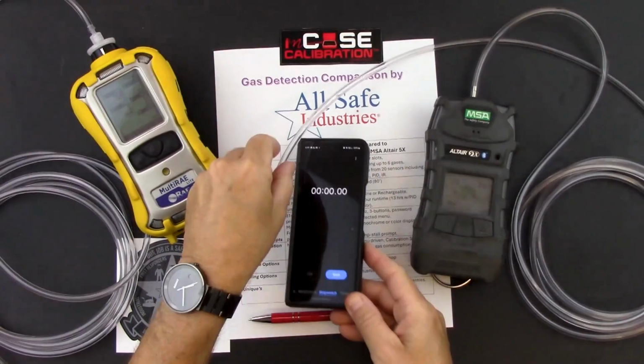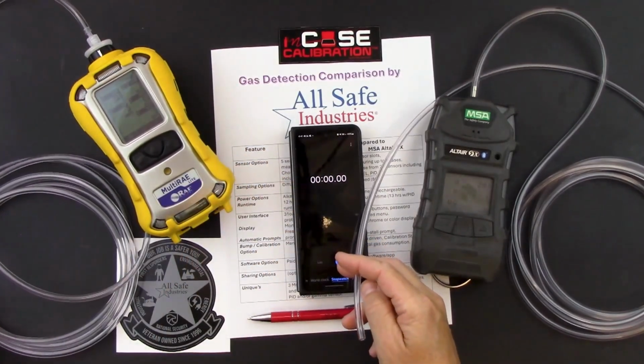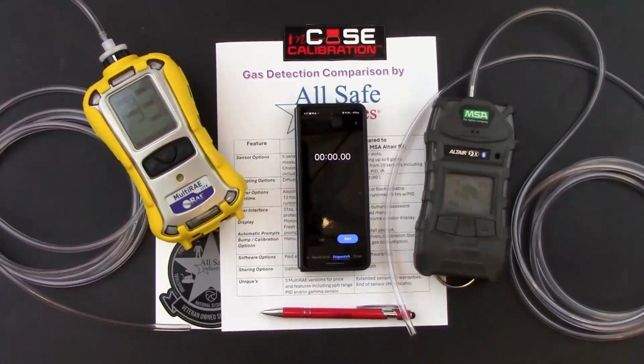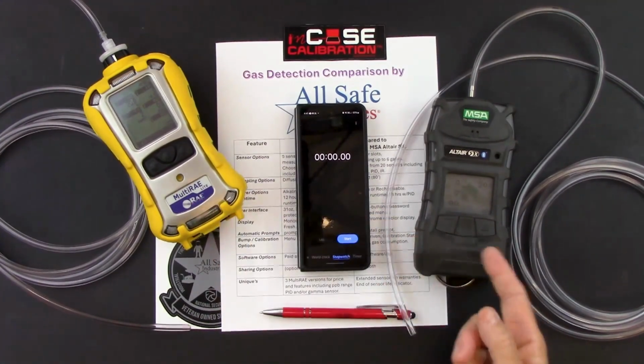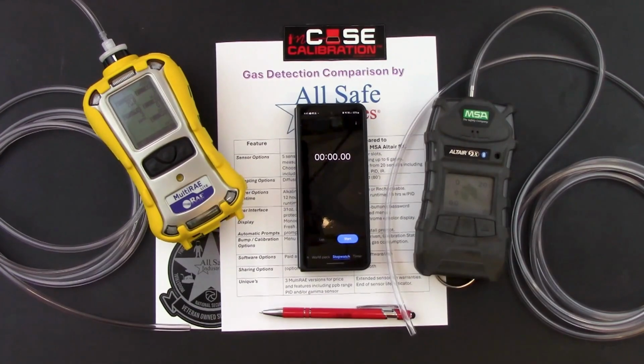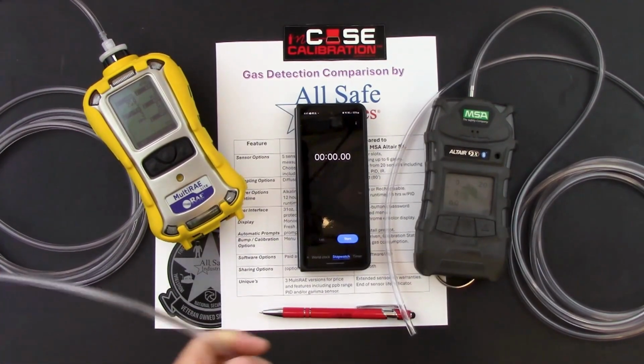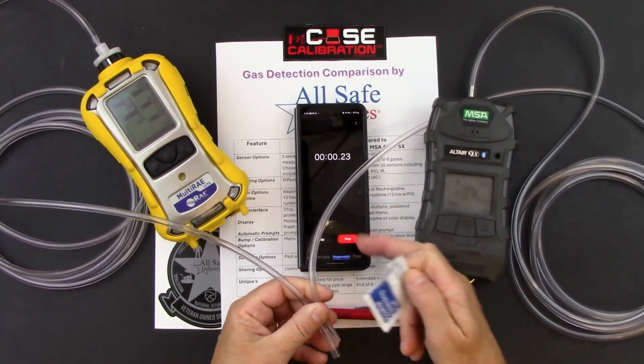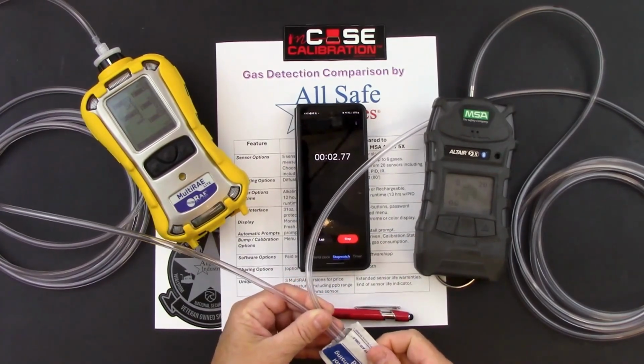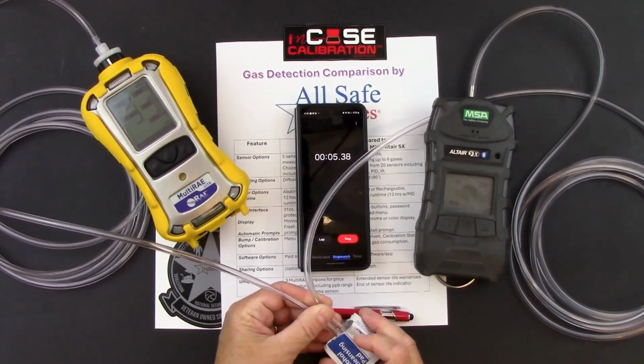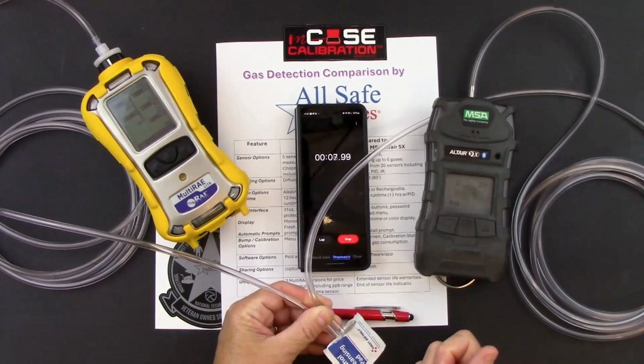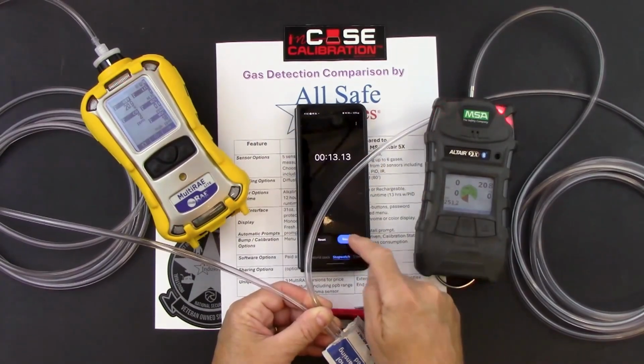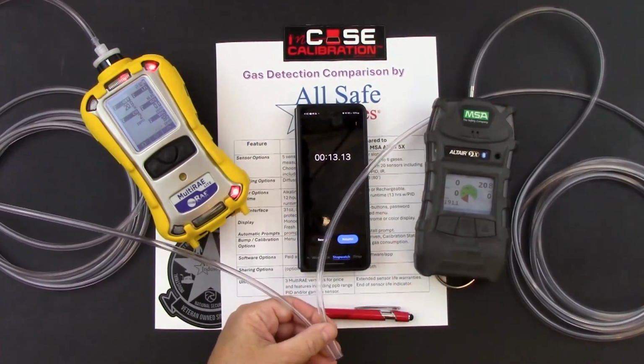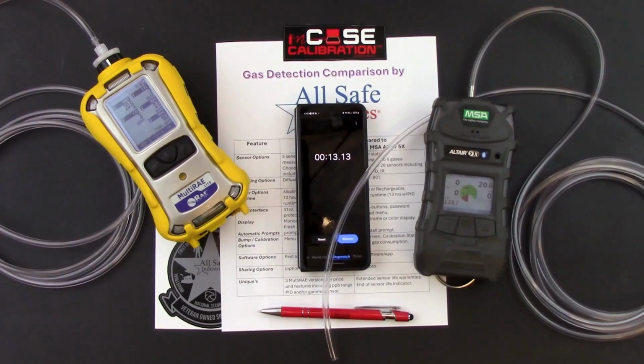I'm going to set a timer. I'm going to grab the ends of my tubes. I'm just going to use a simple alcohol wipe to trigger the PID sensors and also see how quickly these instruments will draw in the sample. So I'll go ahead and grab the ends of my tubes, hit my start timer, and then start sampling the alcohol vapor coming off of this pad. Starting to see reaction on the sensors. Go ahead and stop that. It's about 13 seconds. Pull the alcohol wipe away.